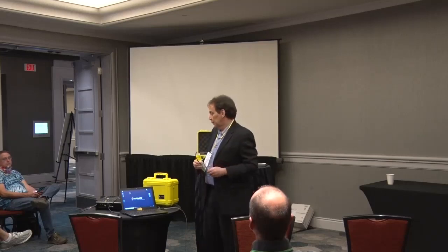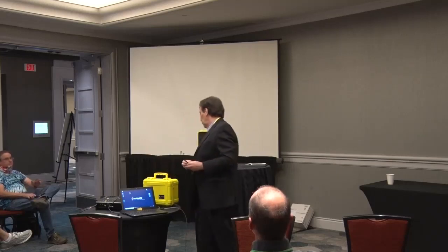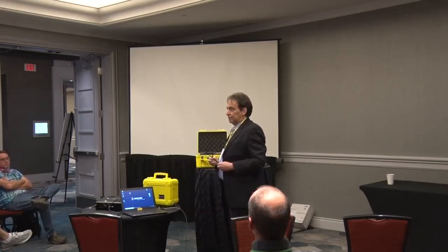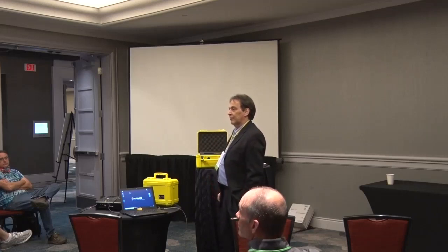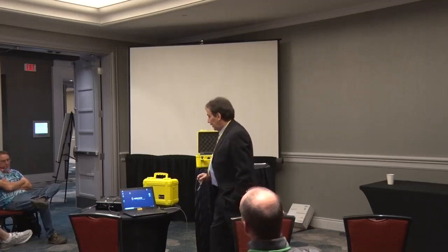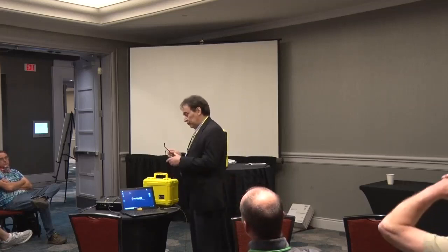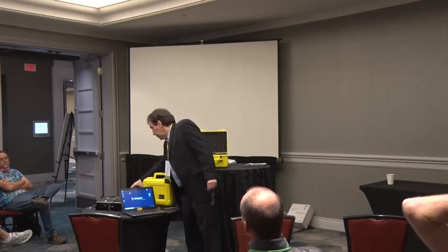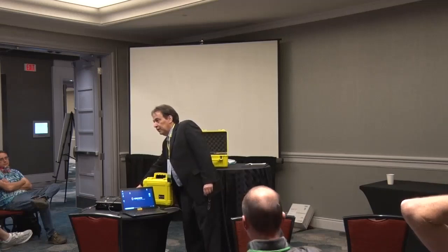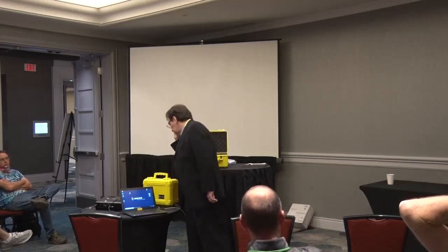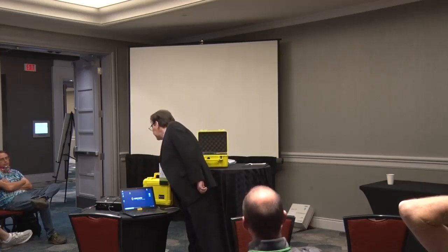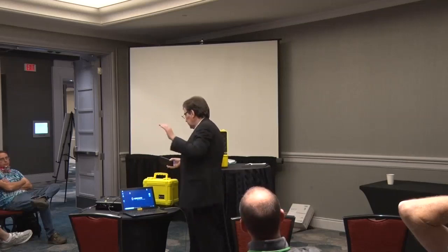Does that have an air pump in it? Yeah, it pumps a little more than half a liter a minute. Because my Johnson sniffer, when you get 1,000 picocuries, you have to set it outside for 15 minutes and suck fresh air through it to get it to go down. Yeah, to a reasonable level again. So we still have radon progeny plated out, but the math helps us compensate for it. What's the reading now? It's reading 0, but it'll bounce back up.